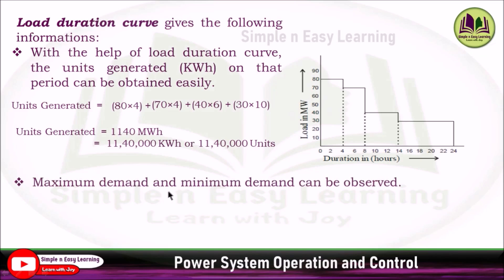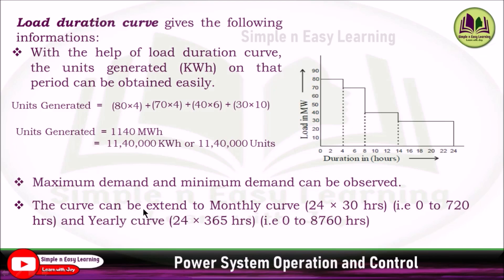The maximum demand and minimum demand can be observed easily from the load duration curve — the maximum demand is 80 megawatt and the minimum demand is 30 megawatt. This curve can be extended to a monthly curve by multiplying by 30 days, giving 24 × 30 = 720 hours, and to a yearly curve by 24 × 365 = 8,760 hours. Using this curve, all this information can be obtained.